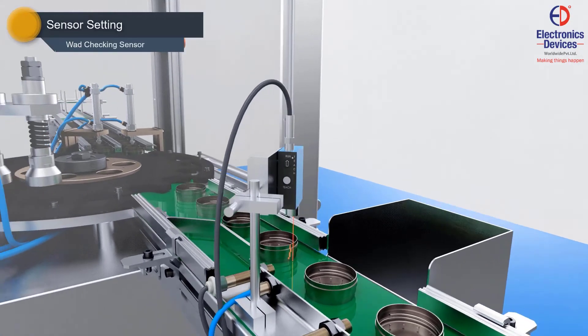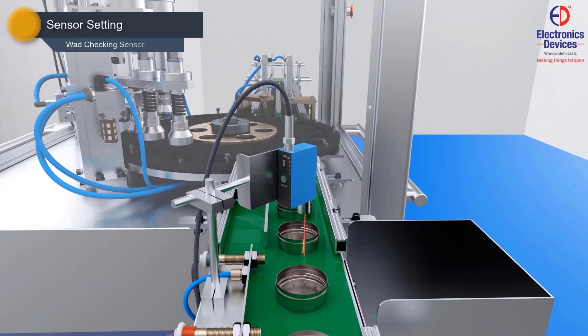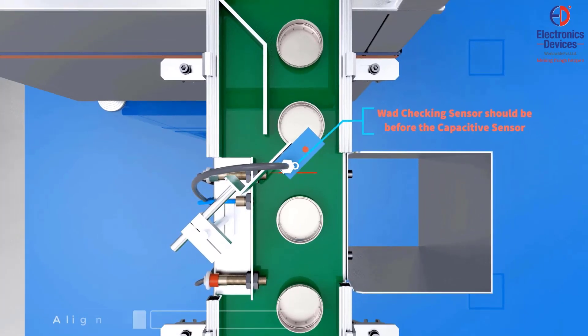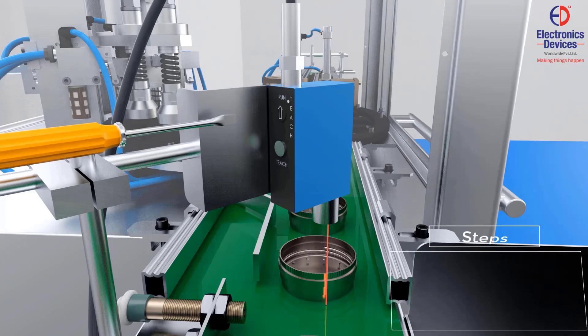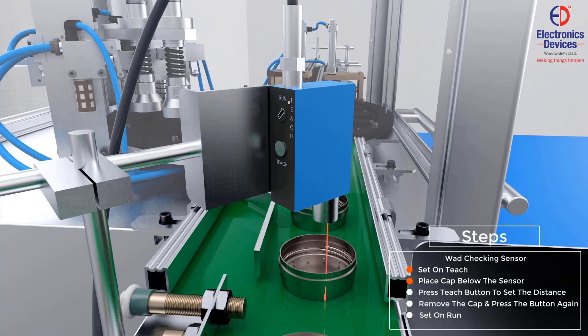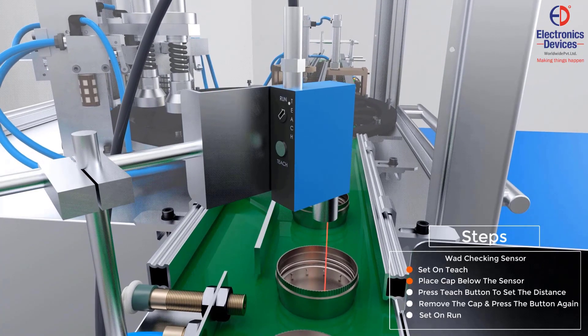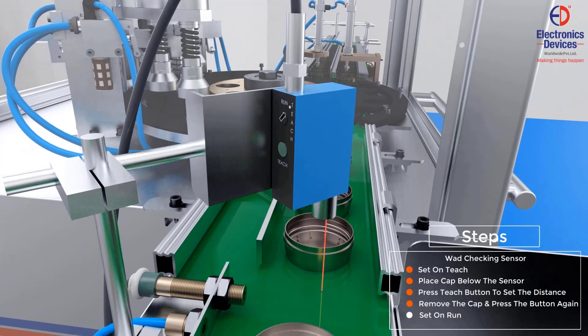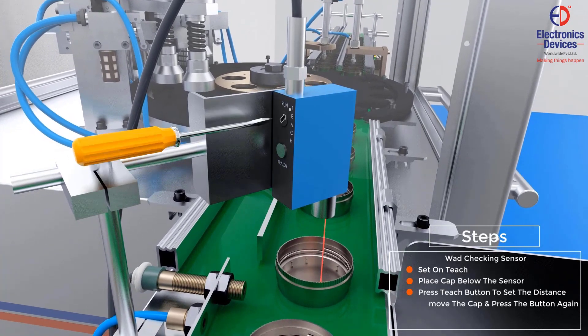Now, set the Wad checking sensor. Align the Wad checking sensor such that it should be before the capacitive sensor. Adjust settings of the Wad checking sensor by pressing teach. Place the cap below the sensor. Press the teach button to set the distance. Remove the cap and press the button again. Set on run.